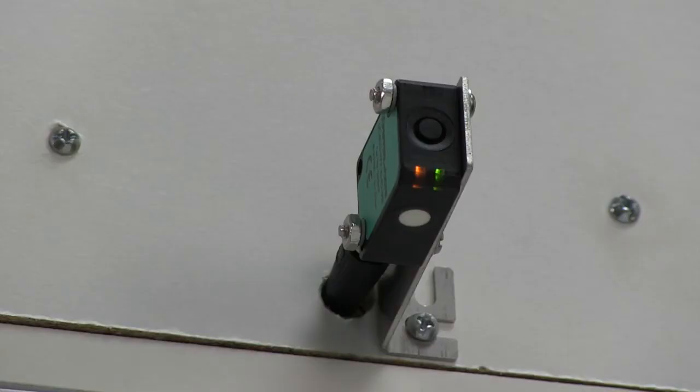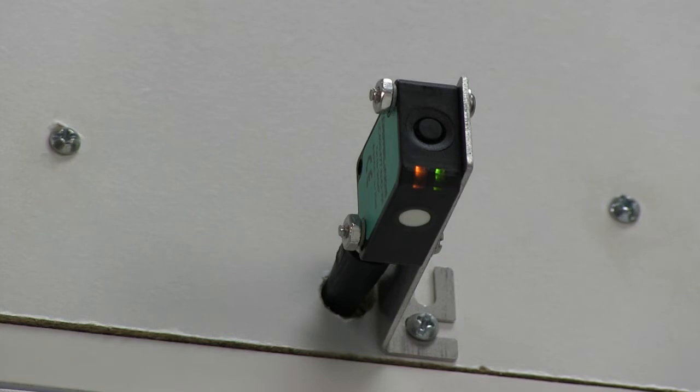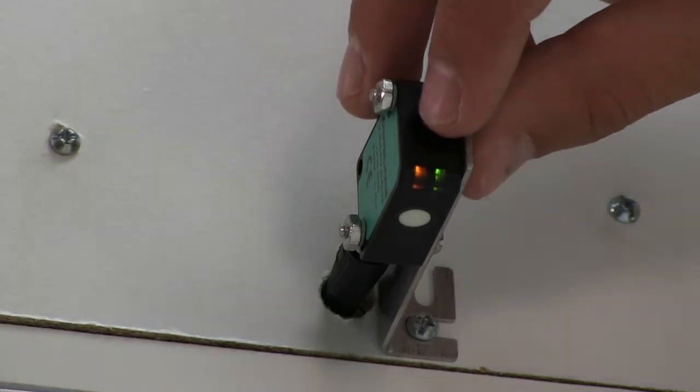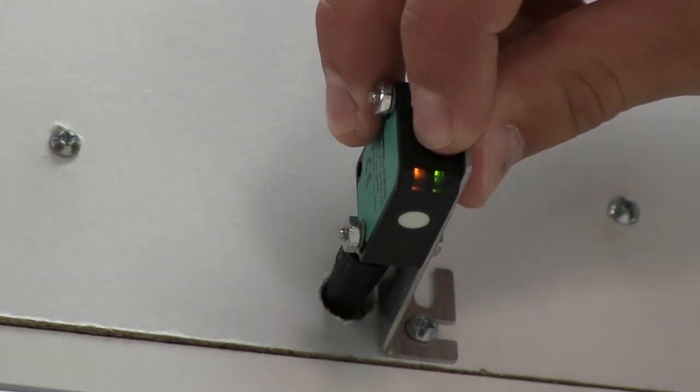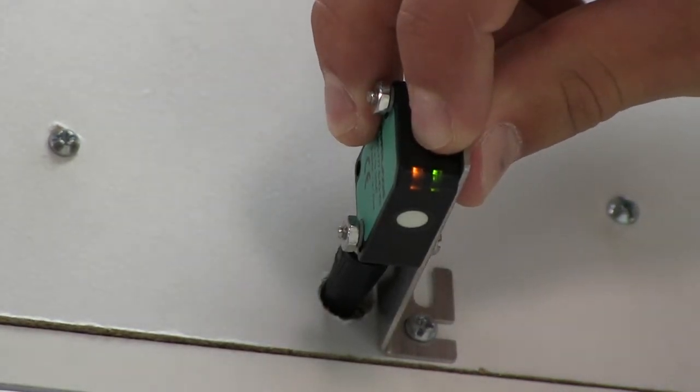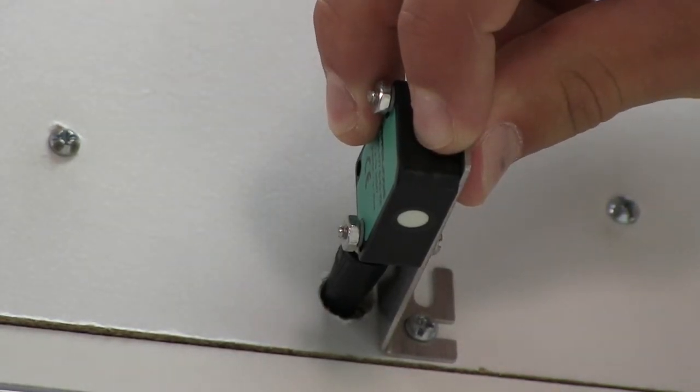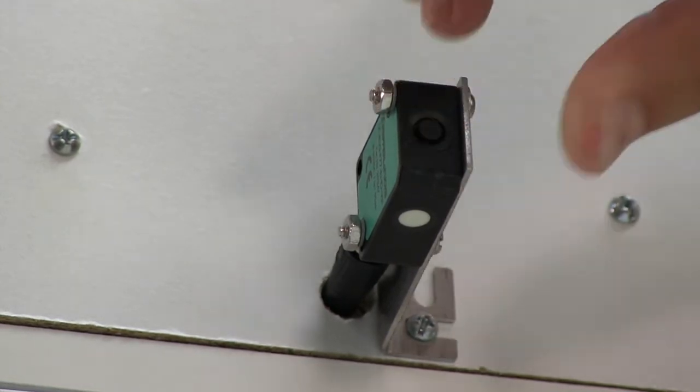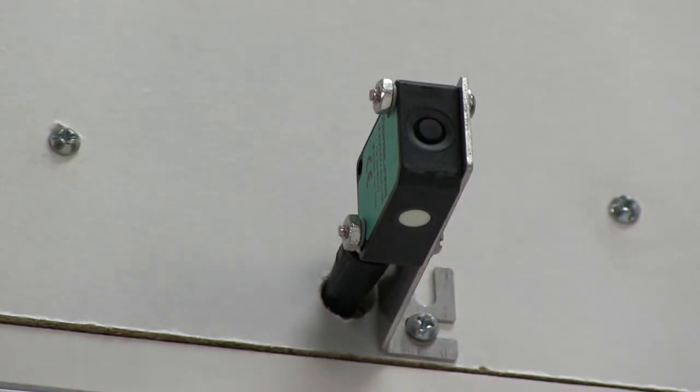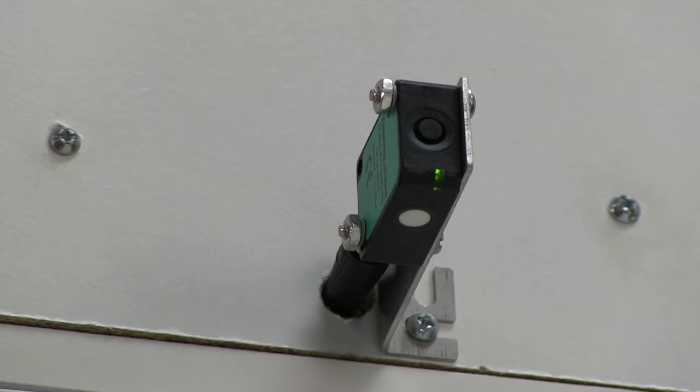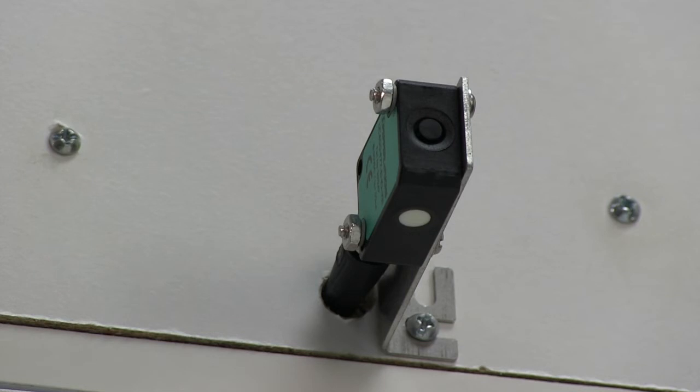Once powered up, the all-important first step needs to take place. In order to communicate with the computer, the analog version sensors need to be put into IO-Link mode. To do this, hold in the push button for five seconds. The green LED should now be flashing. One flash is rising ramp, two flashes is falling ramp, and three flashes is IO-Link mode. Toggle through using the push button until we have three flashes for IO-Link mode.